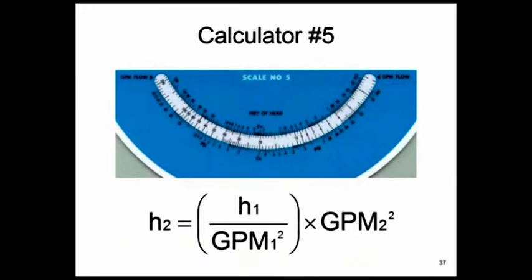So here's the fundamental building block of all balance. Nothing proprietary, just a law that we've got to go by. If I double the flow in GPM, my head goes up 4 times, it goes up by the square. If I cut my GPM in half, my head is 25%. In other words, the difference in pressure drop and flow is the square relationship. So as I double the flow, my pressure drop has got to go up by the square.